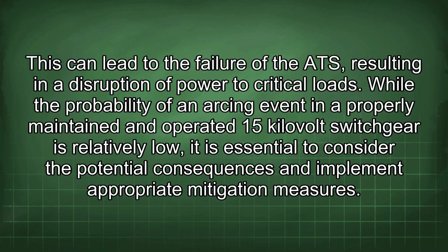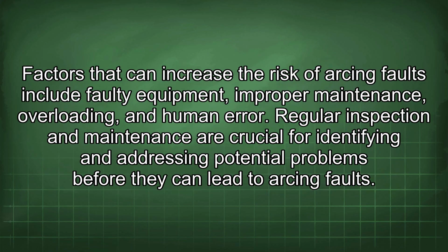While the probability of an arcing event in a properly maintained and operated 15 kV switchgear is relatively low, it is essential to consider the potential consequences and implement appropriate mitigation measures. Factors that can increase the risk of arcing faults include faulty equipment, improper maintenance, overloading, and human error. Regular inspection and maintenance are crucial for identifying and addressing potential problems before they can lead to arcing faults.